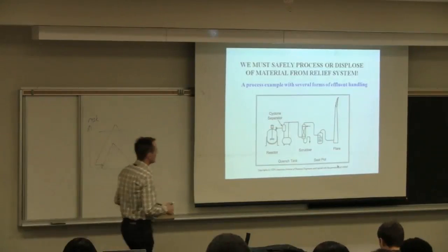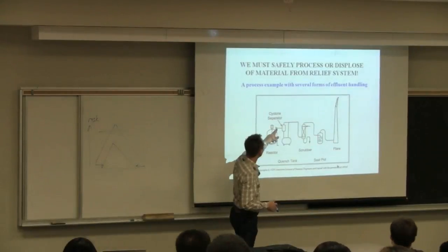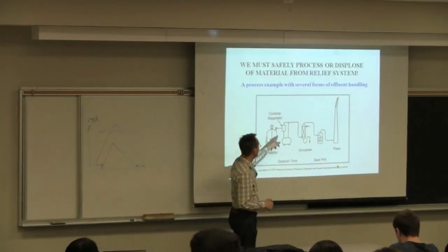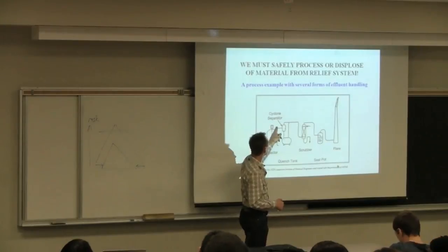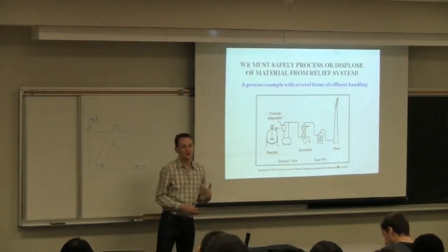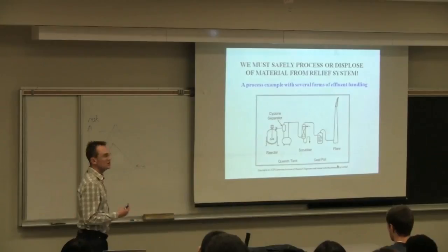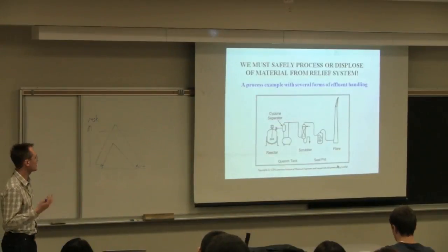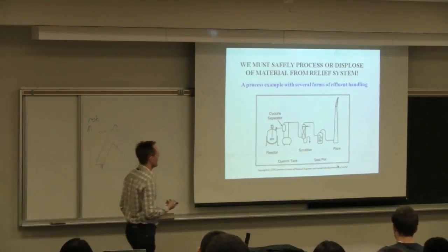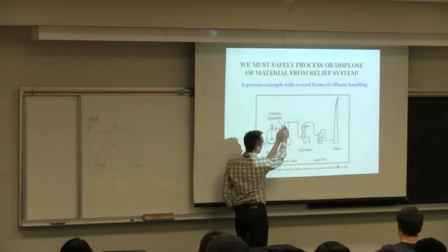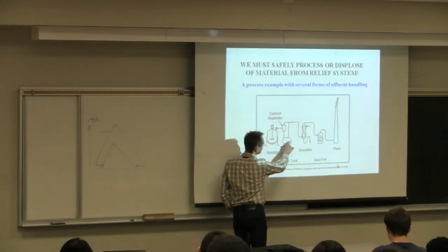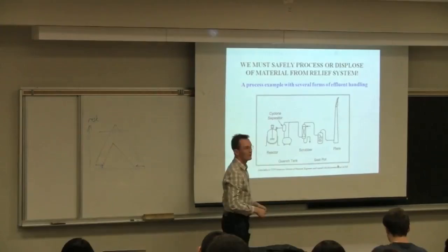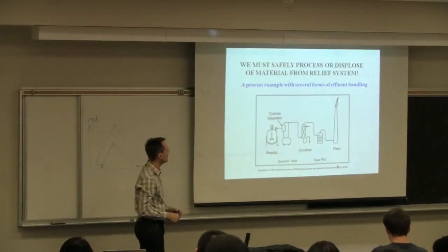So here we've got a contained vessel, pressure relief valve, and if there's solids in the vessel, we can use a cyclone to separate them out. In the case where this pressure is too high, we can use a cyclone there. That's a great idea. It's a totally mechanical device. There's no electrical requirements to operate that cyclone. We're relying purely on the pressure from the reactor to push the material through the cyclone and separate out solids and liquids. Those can be contained in a quench tank. The gas stream can then be scrubbed to neutralize any of the chemical constituents.